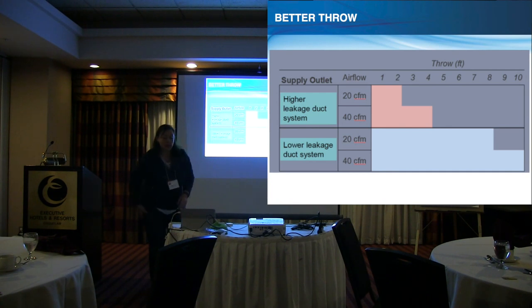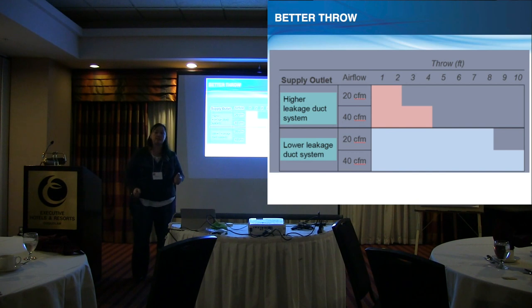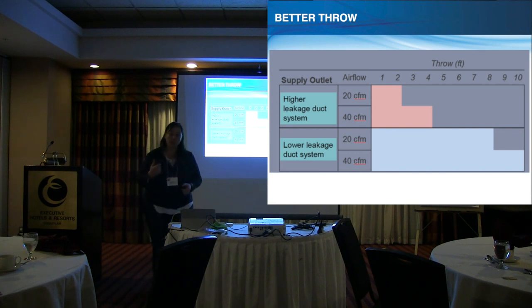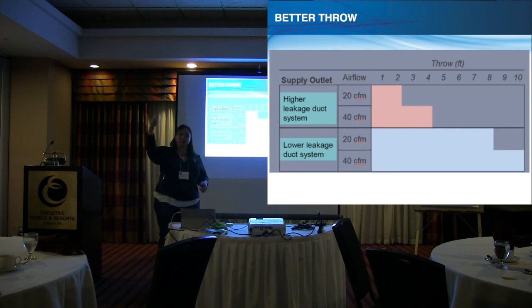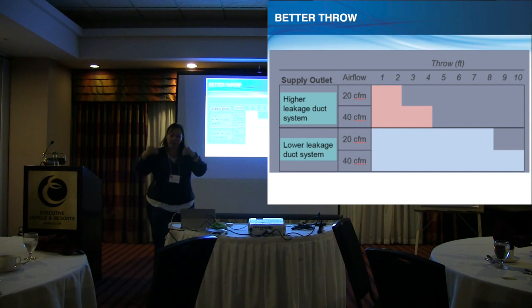So with a traditional system, we've tested this, velocity testing, everything else. So traditional system, you get 3 feet of throw. With our system, we get 9 feet of throw. So it's like sticking your thumb over that garden hose, right, when the water's running. So we want to stick our thumb in there, so decrease the volume of area, get better throw. So we get that 3 feet versus 9 feet.